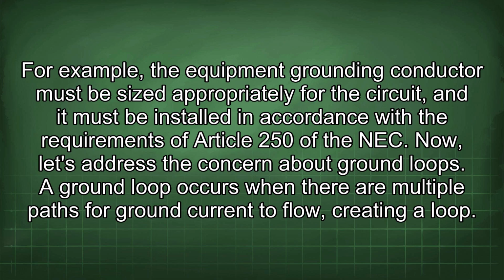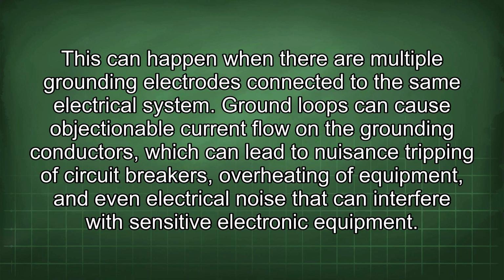Now, let's address the concern about ground loops. A ground loop occurs when there are multiple paths for ground current to flow, creating a loop. This can happen when there are multiple grounding electrodes connected to the same electrical system. Ground loops can cause objectionable current flow on the grounding conductors, which can lead to nuisance tripping of circuit breakers, overheating of equipment, and even electrical noise that can interfere with sensitive electronic equipment.